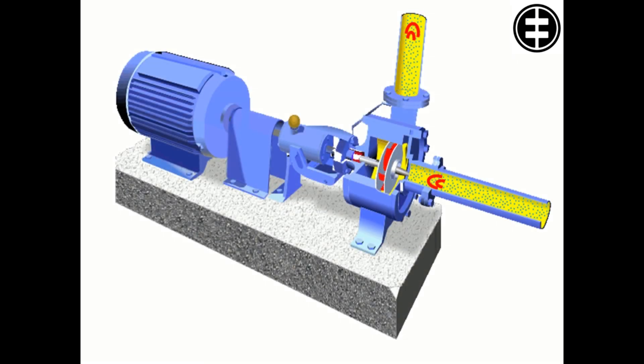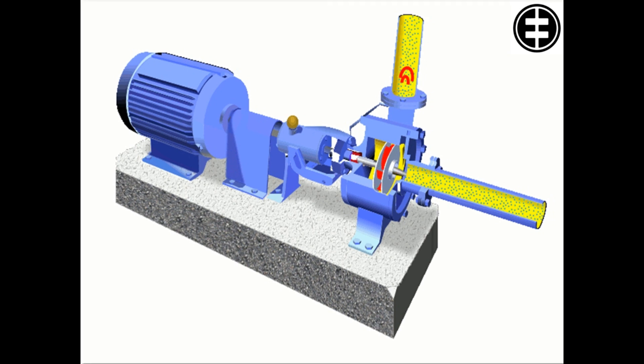Full torque starts or sudden stops can also cause undesirable effects with the application. For example, when a pump is stopped immediately, that can lead to water hammering. A soft starter can be used to reduce the voltage to the pump to prevent water hammering during stoppage.